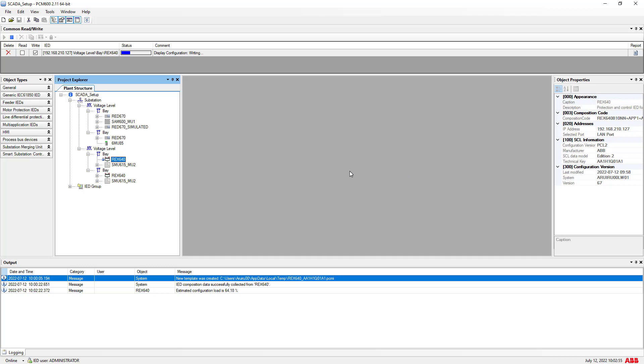Post firmware update, it is also important to check that voltage and current measurements are reading properly. Ideally it should be working fine, but to make sure, also check the functions and the diagnostic information — the IED should not show any warnings or error messages if it is working properly with the latest firmware.